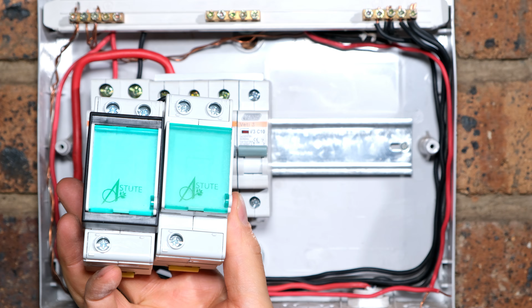Now, in this example, I'll be using this 10 amp circuit breaker. In order to get this circuit breaker to feed your timer, it needs to have the live voltage coming in at the top. In South Africa, the live comes in at the top and the load leaves at the bottom. In other countries they do it differently, with live coming in at the bottom and load going out at the top. But for this video, I'm going to comply with the South African standard, where the supply live comes in at the top rail for these circuit breakers.